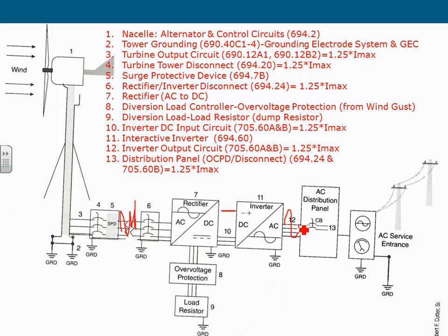The code requires you to also have a disconnect. These are very important for us when we size for electricians. Again, electrically speaking, I apologize to those who are not electrical. The code requires you to have a disconnect on the load side of the rectifier. The DC side, the rectifier, has to have its own disconnect. Now, if the rectifier is within sight of the tower, the same disconnect can act as a disconnect for the tower and for the rectifier. If they are indoors, you have to have a disconnect for that rectifier. Then typically these two units are side by side, and you also have to have a disconnect for the inverter. These are typically one unit, and you have to have a disconnect for the inverter on the AC side.